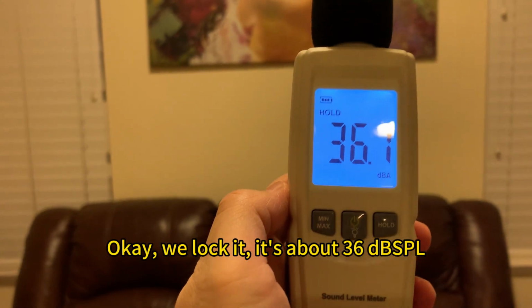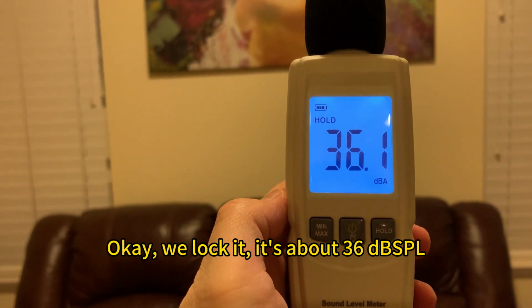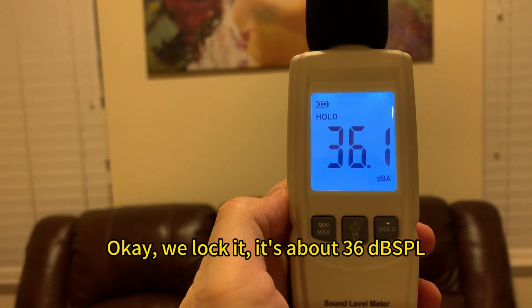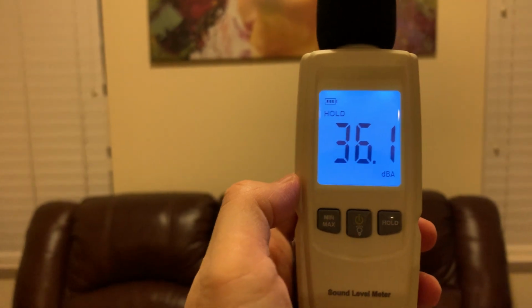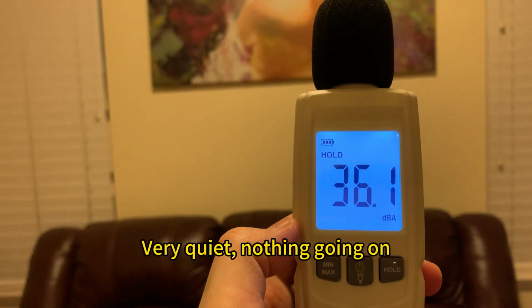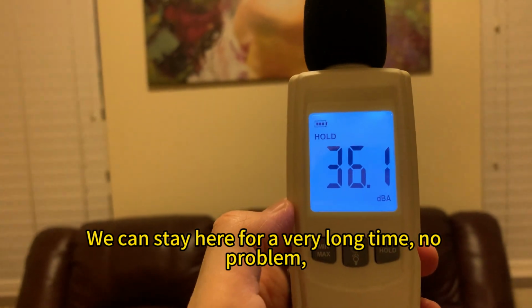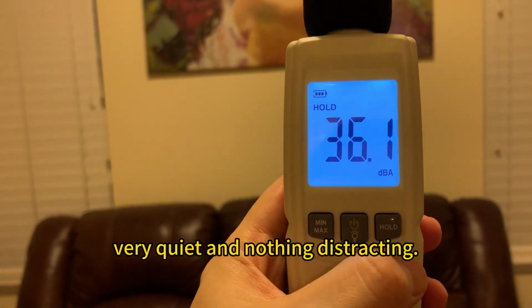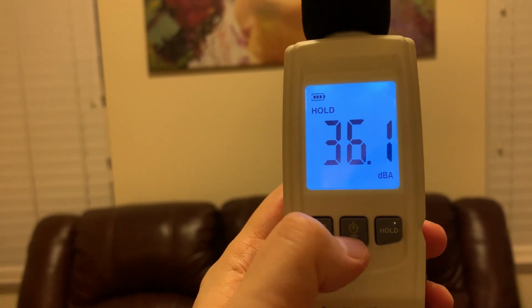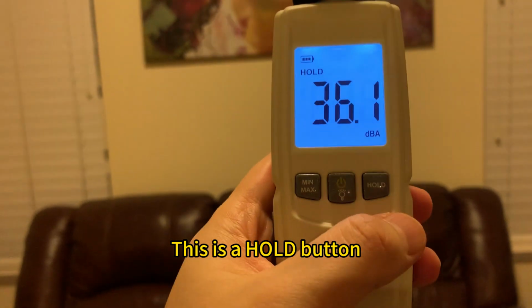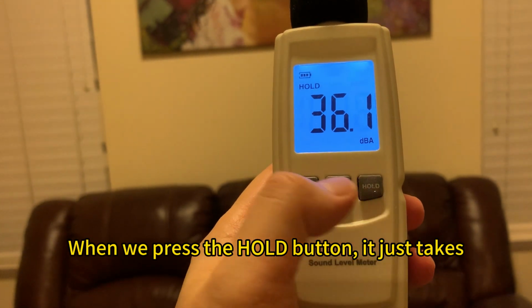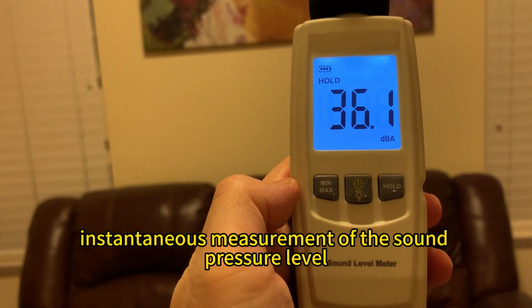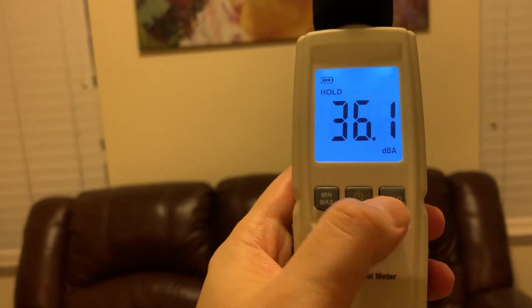Okay, we lock it. It's about 36 dBSPL. And very quiet, nothing going on. We can stay here for a very long time, no problem. Very quiet and nothing distracting. And this is hold button. When we press the hold button, it just takes an instantaneous measurement of the sound pressure level right now.